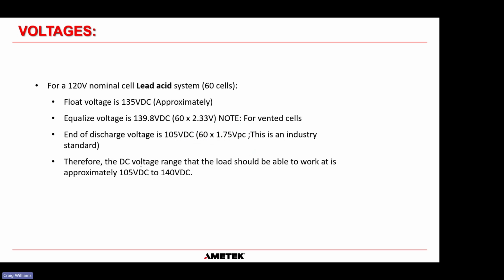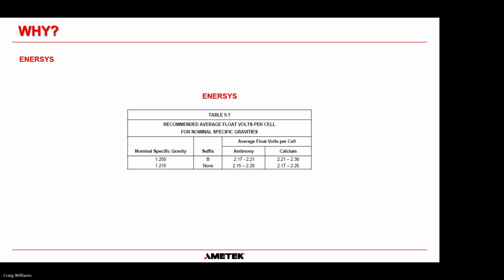So therefore, we can say that the DC voltage range that the load should be able to work at is 105 volts on the low end to 140 volts on the high end, which is just above this equalized voltage. So our DC loads, whatever is connected to this battery, must be able to operate between those two parameters. People say, well, why is that? Because the battery manufacturer has studied this intensely, and they know what the average float voltage per cell should be to maintain the perfect amount of charge and not to overcharge the battery and not to undercharge the battery.